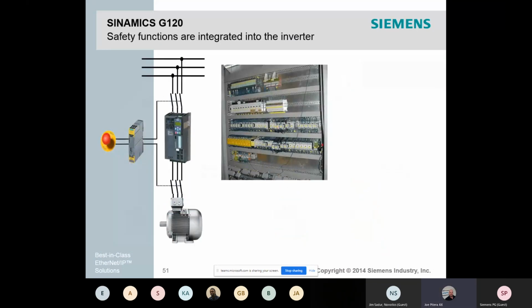Another advantage of the Sinamics G120 is provided by the integrated safety functions. Before Safety Integrated, safety functions required many external components such as safety relays and contactors, dual braking circuits. With the safety functions integrated into the inverter, the functions of the e-stops can be wired directly to the inverter. The functions are certified under SIL 2. You save on components and, as a result, on space and costs. In addition, if you combine a PLC that has safety functions, you can send the e-stop signal directly from the PLC to the drive via Profinet, what we call ProfiSafe network.